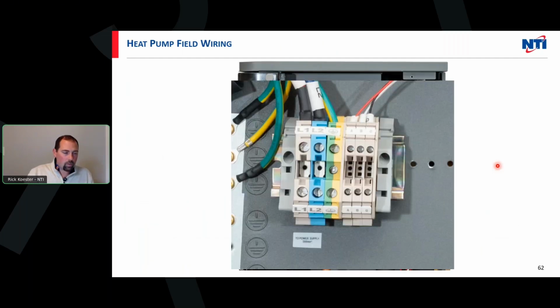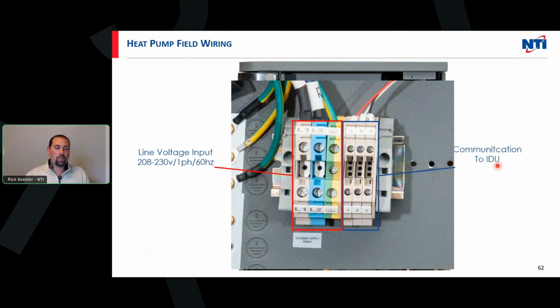At exterior, so the outdoor unit, we do have our input power coming in here, 230, our communication, as you can see there. The systems that we do have that are coming in shortly will have additional terminal blocks there. They'll have the ability to control a circulator from the outdoor unit, as well as having a diverter valve or, you know, mix valve there. So you'll be able to wire everything directly to that. That's going to come in down the road when we start talking about cascades and stuff like that. So stay tuned for that.